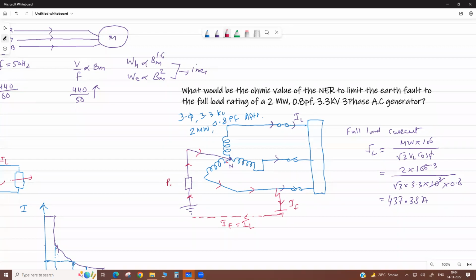Then what is the value of this resistance? Actually, this is one closed circuit. Let us neglect the winding resistance, which is very few ohms. Now, across this closed path, what is the potential applied? In a grounded system, it is the phase voltage, the line to ground voltage. It is divided by the total impedance. Suppose it is Rn only. So what is the fault current? It is known as the earth fault current.